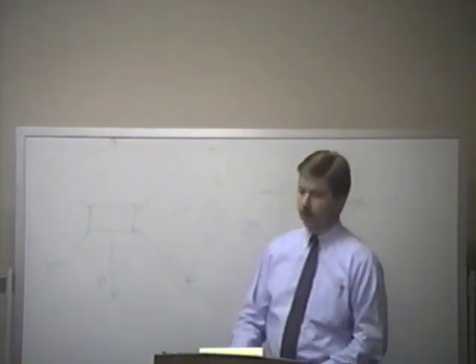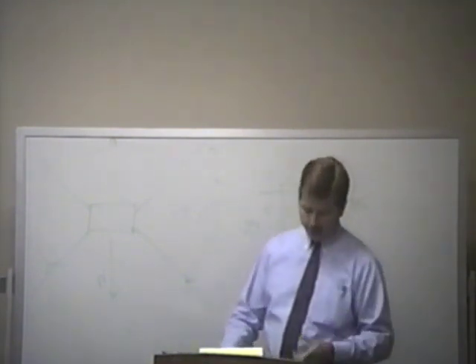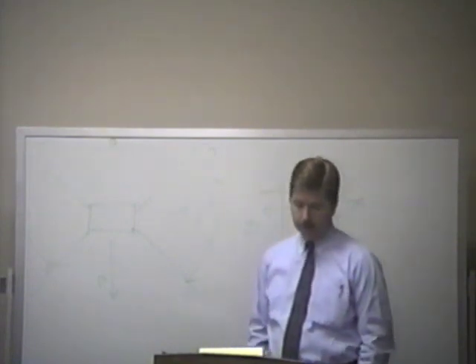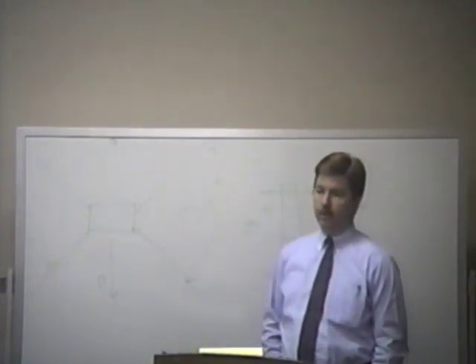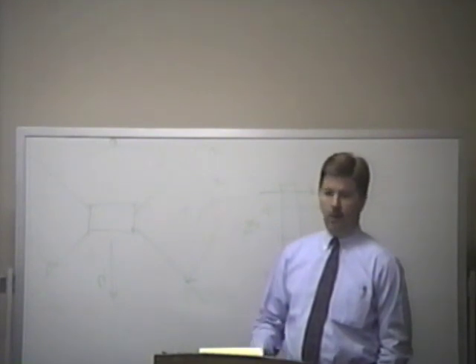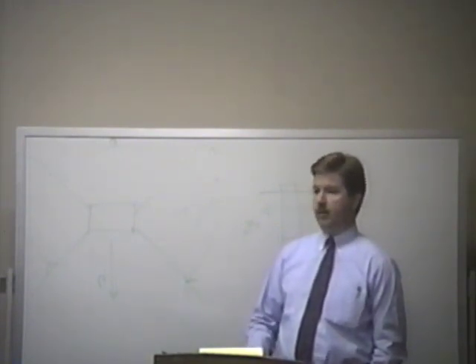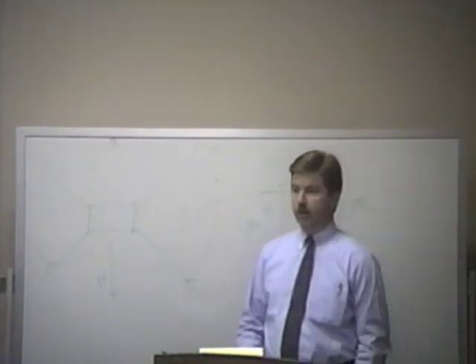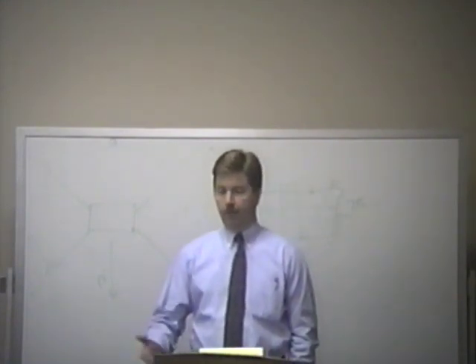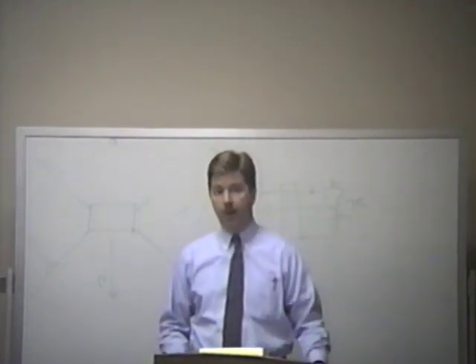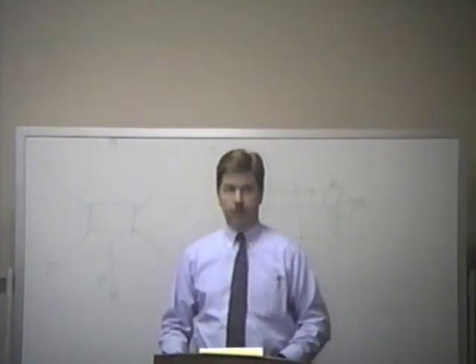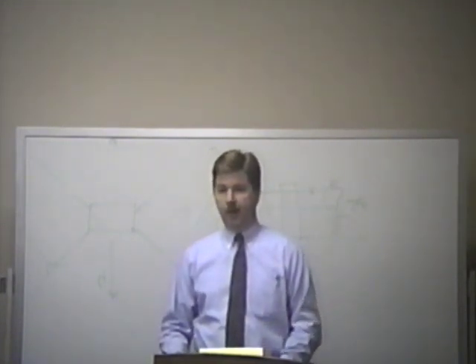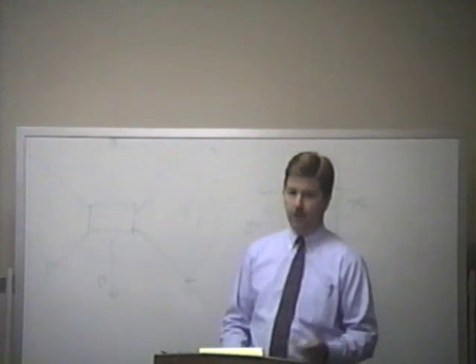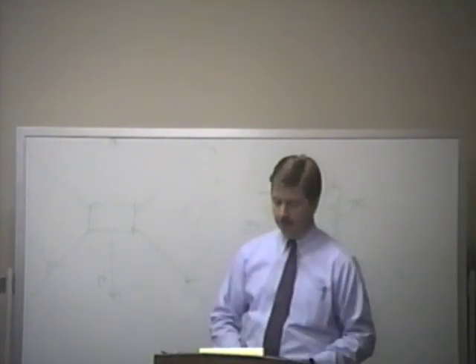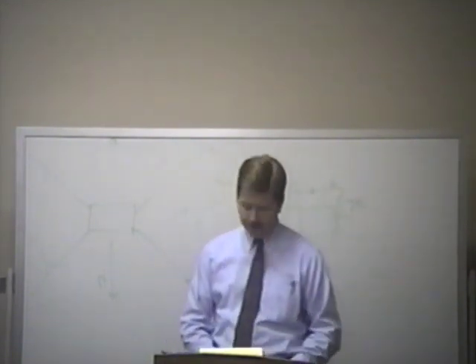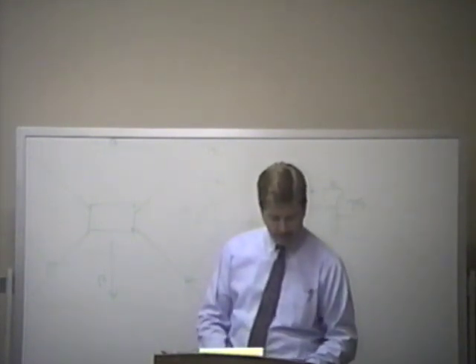Seems pretty wasteful. That's why I bring this up when discussing HID lamps and efficiency, you can see why it's very important. Back to what I said earlier, don't overkill on foot candles. Why provide all this surplus light? All you're doing is creating a byproduct you then have to refrigerate or heat. In the wintertime it's fine, but there are more efficient ways to heat your building than using light bulbs. That's fine if you're raising little chickens and put a light bulb out there with them, but when you've got a lot of people, it's not a very efficient process.